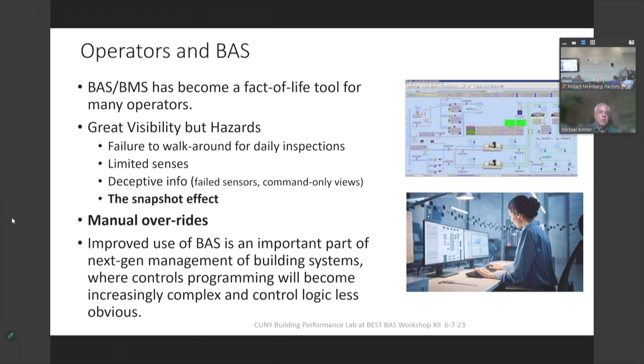We know there's a problem with manual overrides. If an operator gets a phone call or doesn't understand why a piece of equipment is doing something, it's going to go into manual override, and whatever the programming is there, it can be offline for a short or long amount of time after that. I work with many facilities where operators, because they don't trust the BAS system—sometimes for good reason—and they don't know how to adjust it or write in it, so they prefer to operate manually.